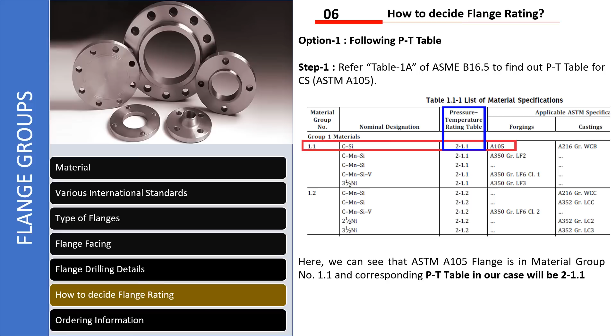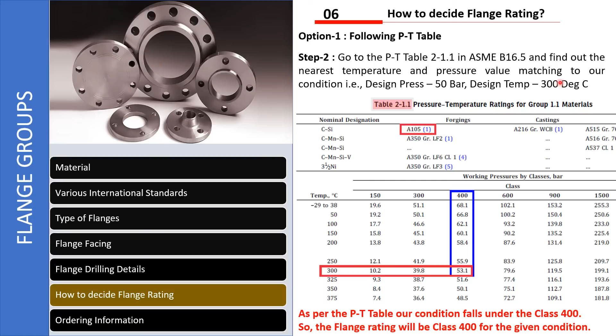First, we will go to the table where we identify this carbon steel material for forging. Then we refer to this table in 16.5. Once we go to this table in 16.5, we can see against 300 temperature where is 50 bar pressure, that is here itself. So for this condition of 50 bar pressure and 300 degrees Celsius, the pressure class will be 400. So we can directly get the class from this table given in 16.5. This is option 1. With respect to pressure temperature conditions, we can classify which class it belongs to.